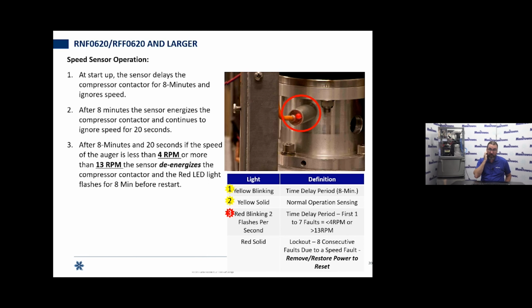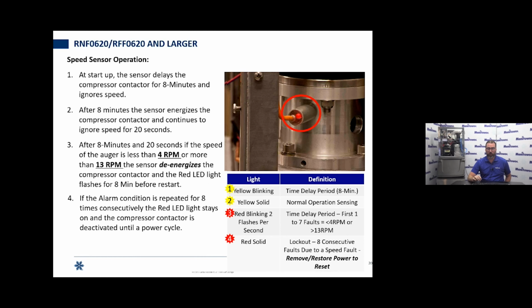Again, I'll go through this again. If we lose RPM at any point, we're going to flash the LED fast flash, 2 flashes per second. That's going to indicate we lost RPM and that we're in another time delay period. And if we unfortunately repeat that 8 times in a row, then we're going to go in a lockout and we are going to see a solid red light.